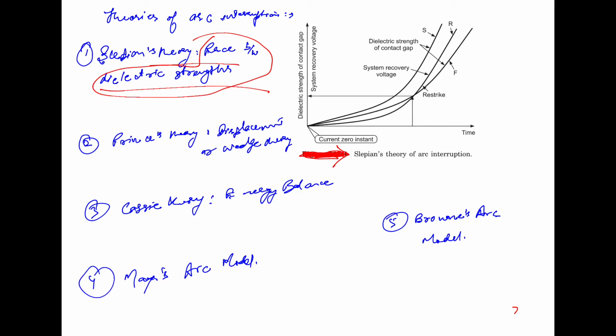In the curve marked F, the dielectric strength, though initially greater than the recovery voltage, loses the race at some point, and hence the arc restrikes and the interruption becomes unsuccessful. So this was the Slepian's theory, which is the race between the dielectric strengths.